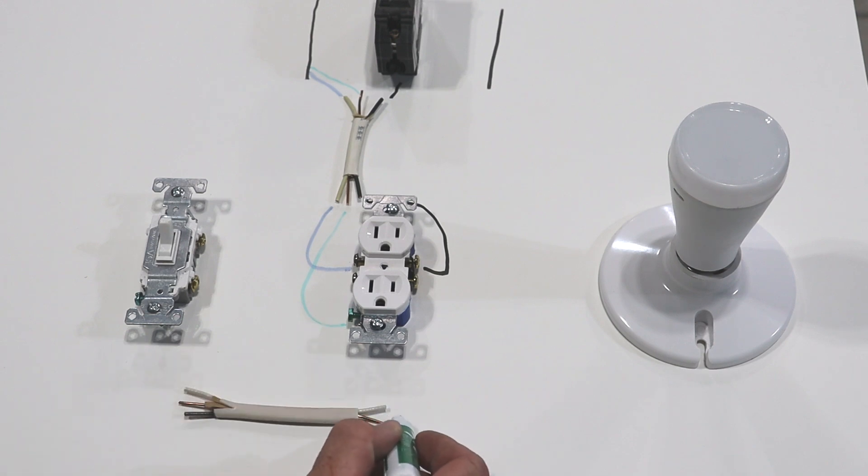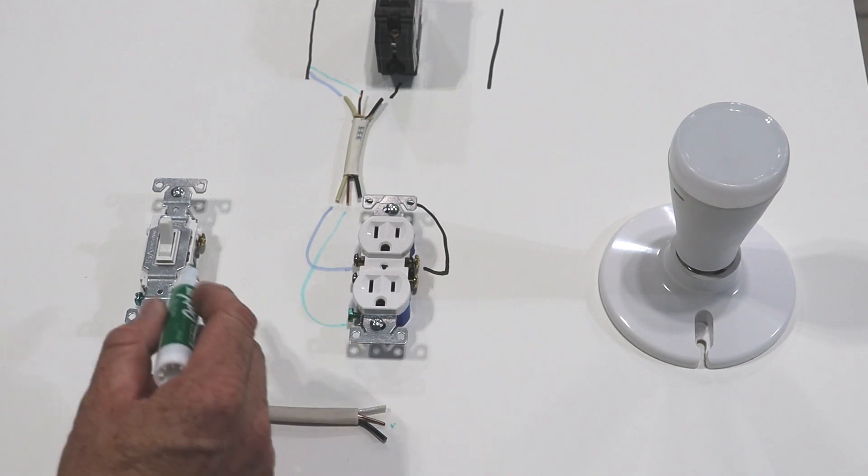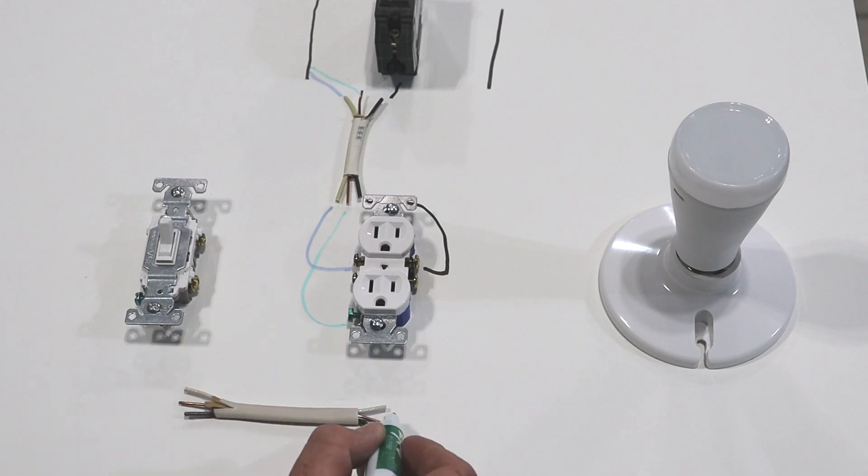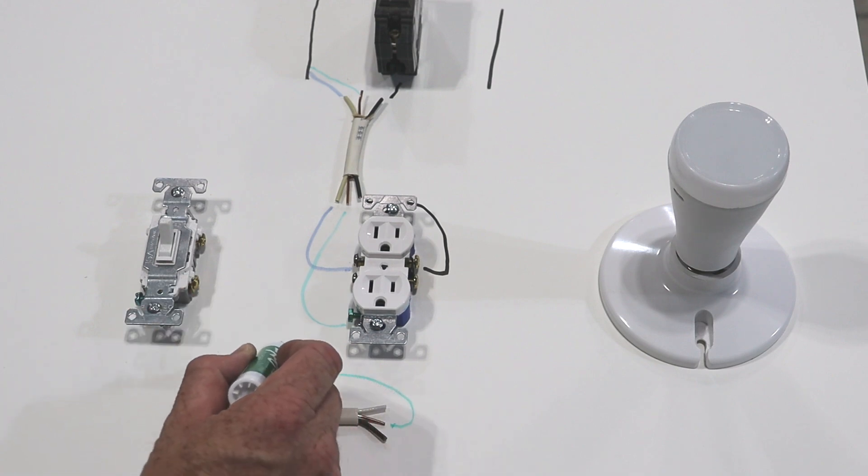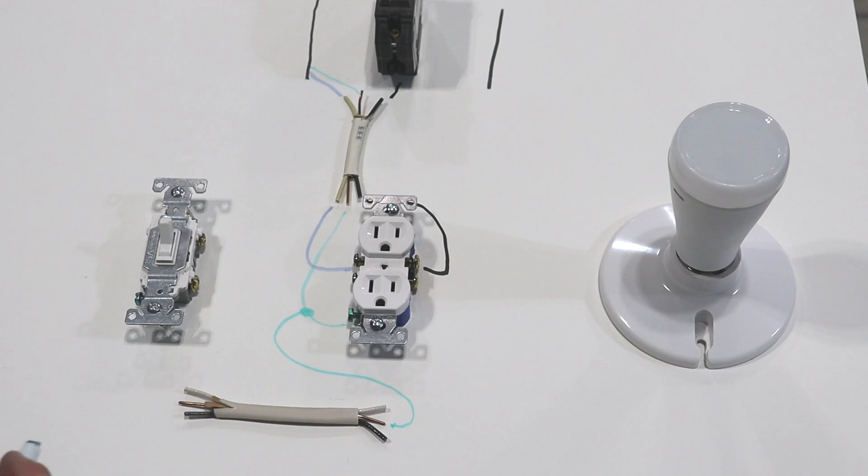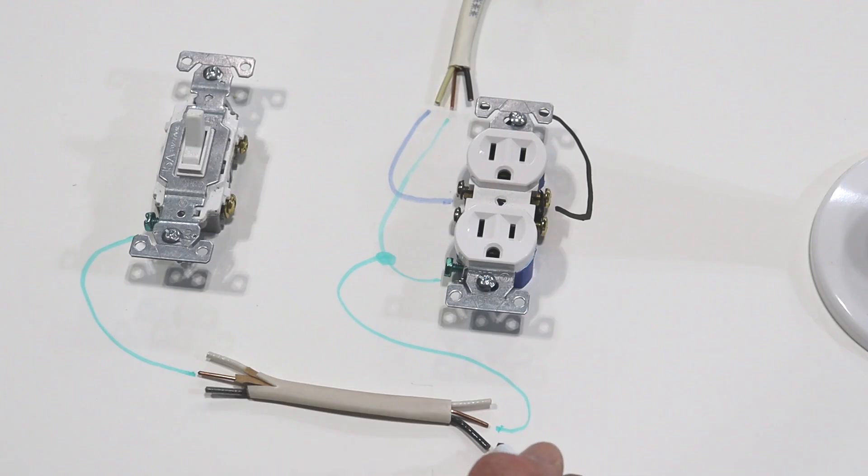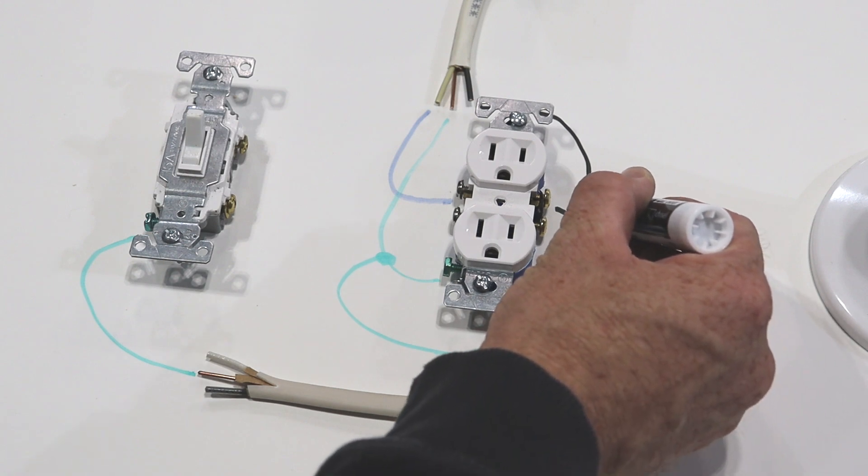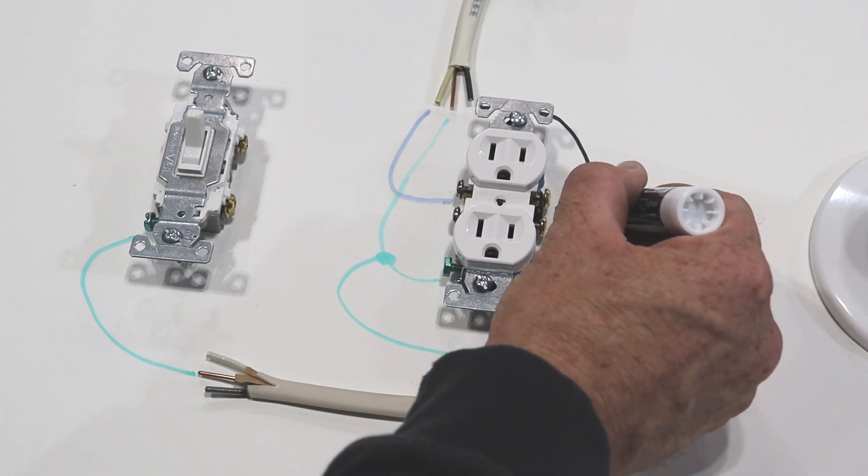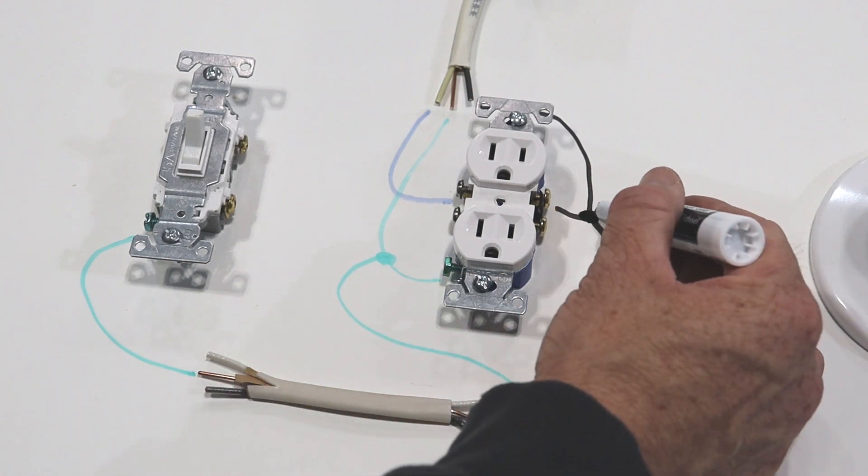We'll come off from our Romex that's going to go up to our switch and we'll come over here and we'll wire nut this together. Then we'll take our ground wire and connect it to the screw on the switch. Then what we're going to do is we're going to run our black wire over to our other black wire and make a pigtail here, so this would be wire nutted.